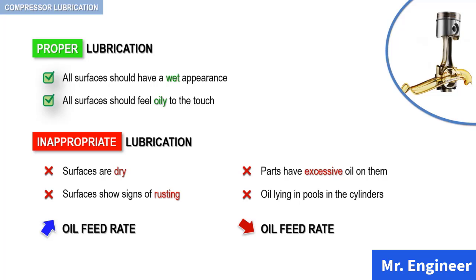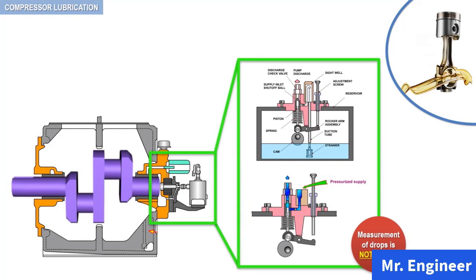Keep in mind, for your own safety, in the operation of air compressors, over-lubrication of the cylinders and the subsequent carryover of excess oil to the downstream piping system causes excessive deposits and the real possibility of explosion or fire. Finally, keep in mind that the biggest problem with box lubricator pumps is that they either pump too much oil or no oil at all. They are difficult to adjust and maintain, they often are driven too fast to deliver the required amount of oil, and they cannot provide protected delivery. Any pump can stop without being noticed, causing serious damage to the compressor cylinders, packings, and other components.